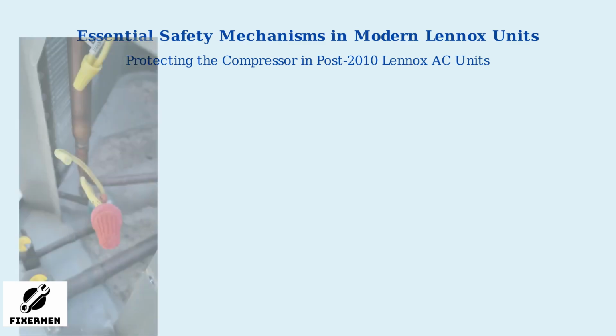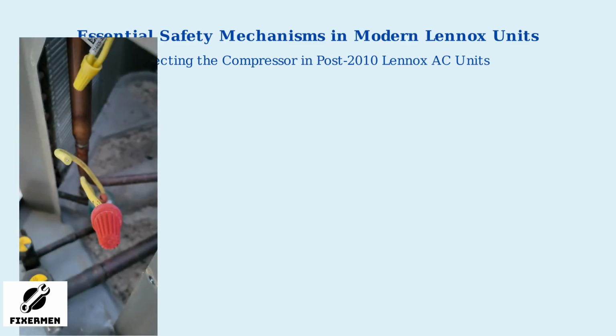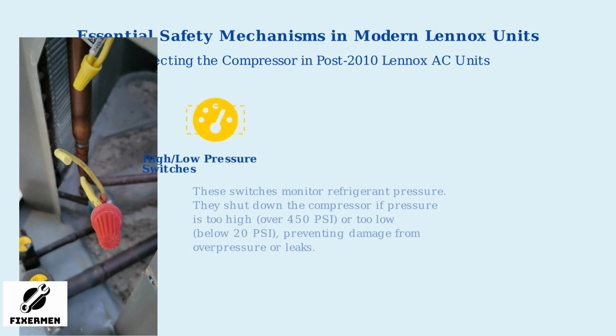Modern Lennox AC units built after 2010 include essential safety mechanisms designed to protect the compressor from damage. These features prevent issues like overpressure, overheating, and rapid cycling that could lead to expensive failures. The first key safety mechanism is the high and low pressure switches. These monitor the refrigerant pressure in the system. If pressure gets too high above 450 psi or too low below 20 psi, the switches automatically shut down the compressor to prevent damage from overpressure or leaks.